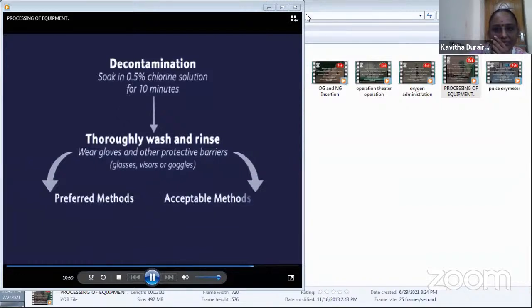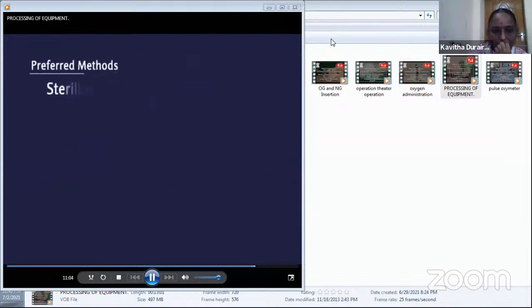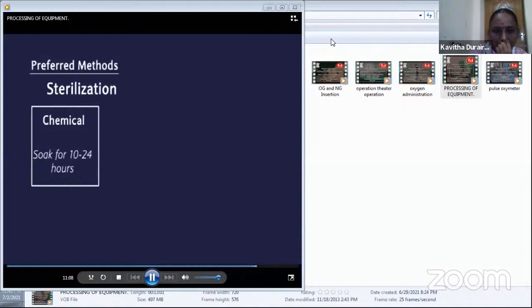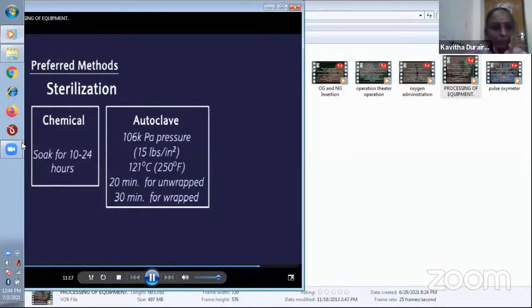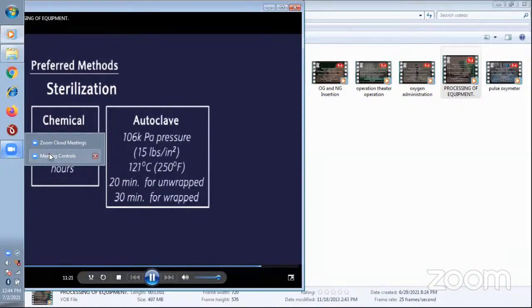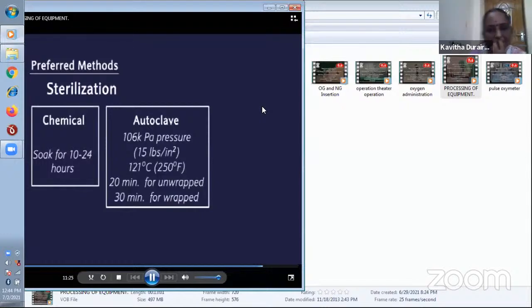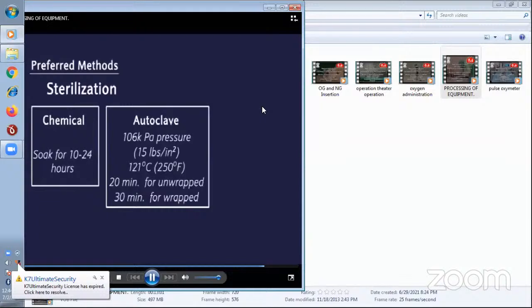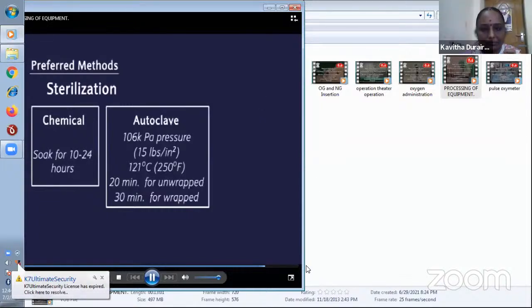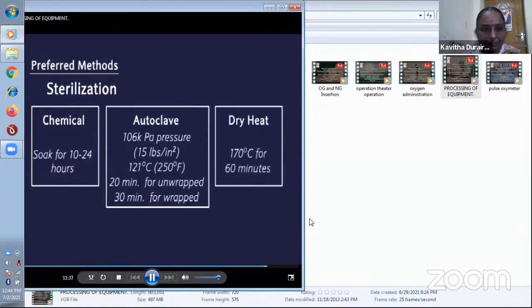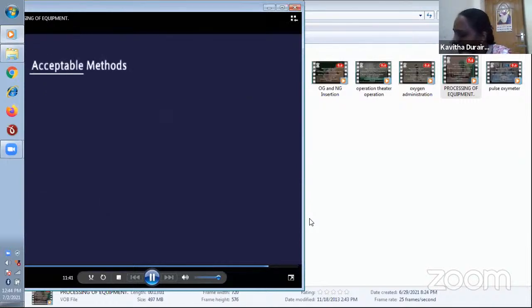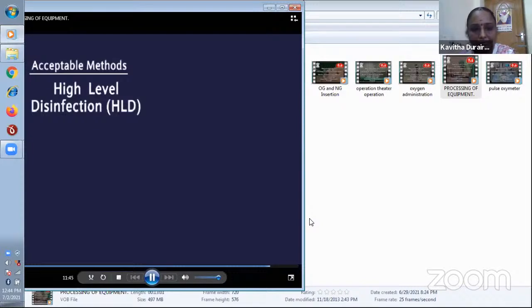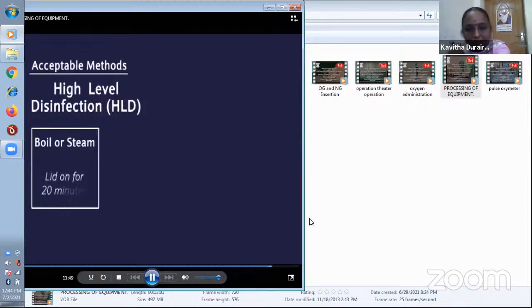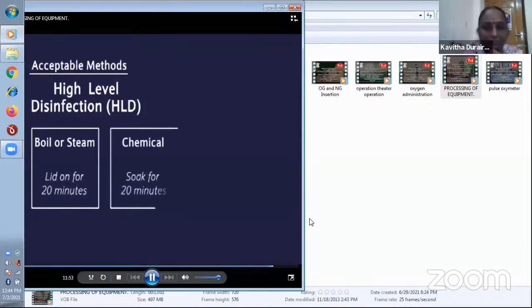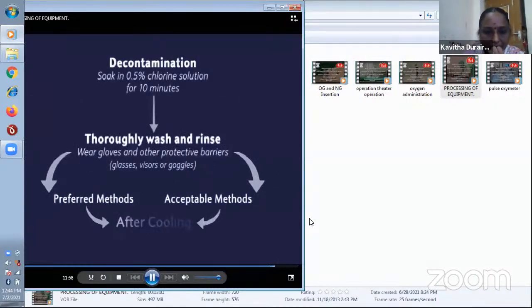Preferred methods. Acceptable methods. Preferred methods. Sterilization. Chemical: soak for 10 to 24 hours. Autoclave: 106 kilopascal pressure, that is 15 pounds per square inch, 121 degrees centigrade, that is 250 degrees Fahrenheit, 20 minutes for unwrapped and 30 minutes for wrapped. Dry heat: 170 degrees for 60 minutes. Acceptable methods: high-level disinfection, that is HLD, boil or steam, lid on for 20 minutes. Chemical: soak for 20 minutes. After cooling, use immediately or store.